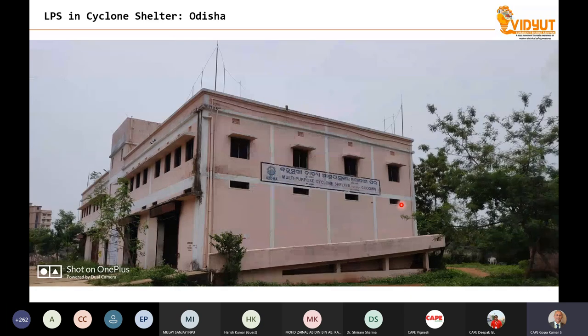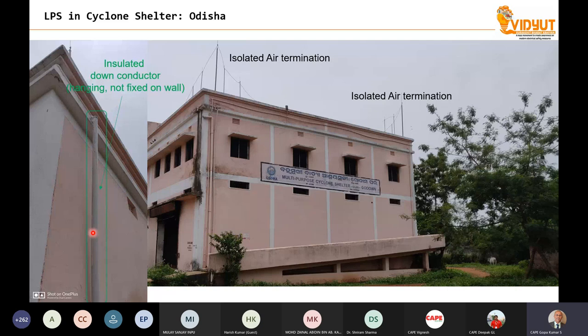This is the cyclone shelter. Isolated air termination. And you look at this on the left side. There is a pipe, and through this pipe this special down conductor is running. It is an established fact that down conductors must be fixed to the building very strongly. You cannot hang it loose, because the mechanical forces created by the lightning are very, very heavy. If your fixing is not proper, then it could create an explosion. So you are supposed to fix it very firmly, whereas this down conductor is hanging through a pipe.